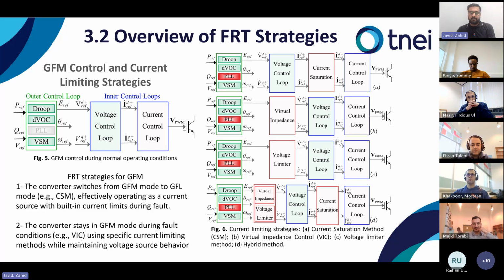The FRT strategy can incorporate additional goals beyond current limiting, such as supporting grid voltage and frequency stability while complying with the host grid's FRT requirements. The way a GFM resource behaves during the fault is primarily determined by this FRT strategy, and it is an active research topic, and there is no universal agreement on the best approach. While GFL inverters typically rely on the current saturation method and PLL-based synchronization during fault, some GFM schemes adopt similar methods, switching to PLL synchronization when a fault occurs and the current exceeds the set limits. However, GFM inverters also offer unique possibilities for fault management that differ significantly from GFL schemes.